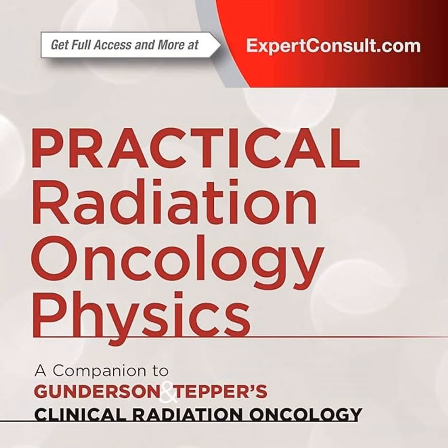Exactly. And the physics requirement for both is absolute precision in calibration. You use an air-filled well chamber to measure them. I know the goal is to find the sweet spot in the chamber. Yeah, you are basically looking for the position of maximum reading. When calibrating an HDR source, the physicist literally steps the radioactive source through the well chamber millimeter by millimeter. Oh, wow. They record the electrical current at each stop until they find the peak reading. The golden rule in the clinic is that your physical measurement must match the manufacturer's shipping certificate within 3%. 3%, that's strict. It is. If it's off by more than 5%, you halt everything. You do not treat the patient, you just send it back.